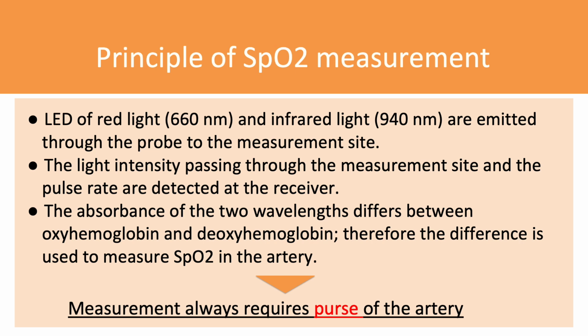Now, we will describe the principle of SpO2. Red light of 660 nanometers and infrared light of 940 nanometers are emitted from the probe to the measurement site, and the light intensity and pulse rate passing through the measurement site are detected at the photosensitive area. Percutaneous arterial oxygen saturation is measured by using the fact that the absorbance of the two wavelengths differs for oxyhemoglobin and deoxyhemoglobin. The measurement always requires an arterial pulse.